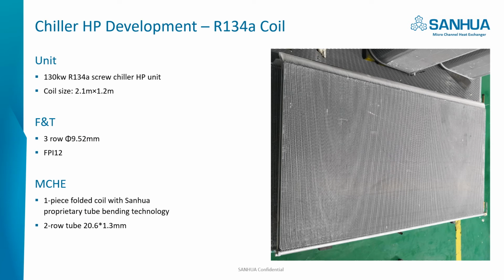The screw chiller normally uses R134A as the refrigerant, so we designed the coil also for the air-cooled screw chiller. This is a unit with 130 kilowatts capacity. The coil size is the same as the 410A coil. The fin tube heat exchanger is a 3-row 9.5 mm fin tube heat exchanger. The fin density is 12 fins per inch. For microchannel, we used the same design as the 410A, so it can be a standard coil for both applications.